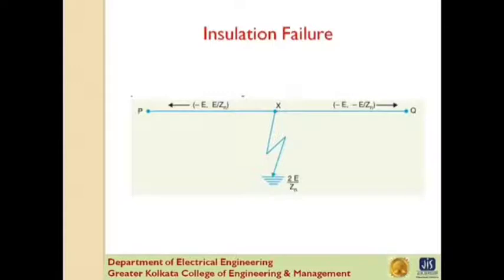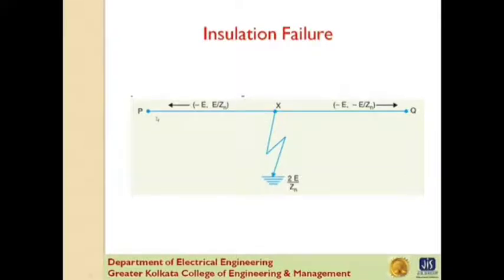Next is insulation failure. The most common case of insulation failure in the power system is the grounding of a conductor, which may cause overvoltages in the system. Suppose a line at potential E is earthed at point X. The earthing of the line causes two equal voltages of −E to travel along XQ and XP, containing currents of −E/Zn and E/Zn respectively. Both these currents pass through X to earth, so the current to earth is 2E/Zn.